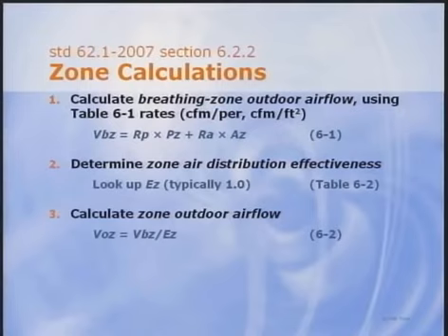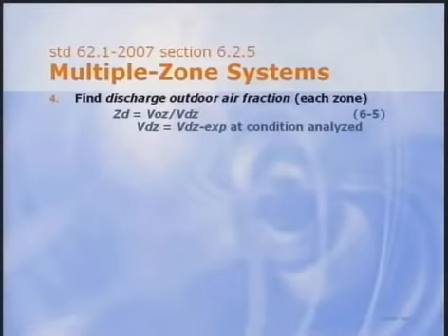Zone outdoor airflow calculations are straightforward. We covered them earlier. These zone calculations are used to find how much outdoor air must be supplied to each zone, both in the breathing zone and at the diffusers. But for multiple zone systems, 4 more calculation steps are needed to find out how much outdoor air to introduce at the intake damper. I mentioned these equations earlier when I talked about ventilation reset control, but here I'll go through the calculations in more detail. Like the first 3 steps, the 4th step applies to each zone. Find the fraction of outdoor air needed in the discharge airstream. For design purposes, use the minimum expected discharge airflow at the condition being analyzed. This minimum may or may not equal the reheat minimum setting for the VAV box. More about this in a minute.